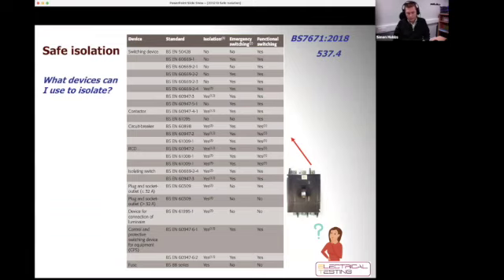I've put a picture there of an old BS 3871 circuit breaker. You might know them as a Crabtree C50 or that type of thing. They're not listed in the approved devices within BS 7671, as we can see here. So the question is, should they be used for isolation? Well, that British Standard was superseded by BS EN 60898. It doesn't mean that they are defective and shouldn't be used, but if we were carrying out an inspection, it might be something that we flag up as an observation or a defect. And certainly they're potentially devices that are reaching the end of their life.